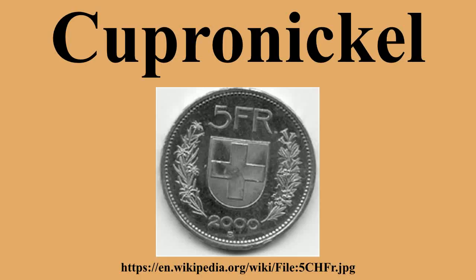Applications: marine engineering. Cupronickel alloys are used for marine applications due to their resistance to seawater corrosion, good fabricability, and their effectiveness in lowering macrofouling levels. Alloys ranging in composition from 90% Cu 10% Ni to 70% Cu 30% Ni are commonly specified in heat exchanger or condenser tubes in a wide variety of marine applications.